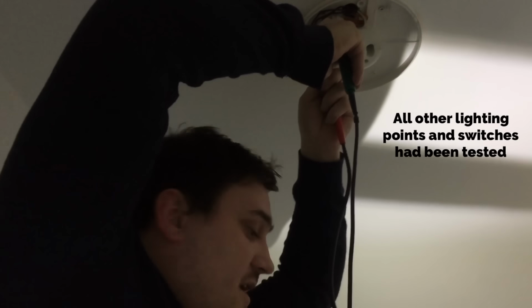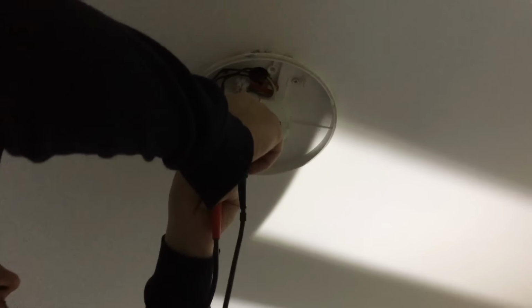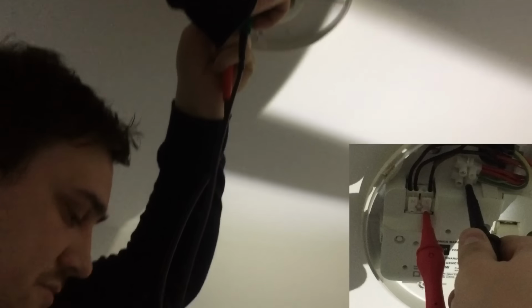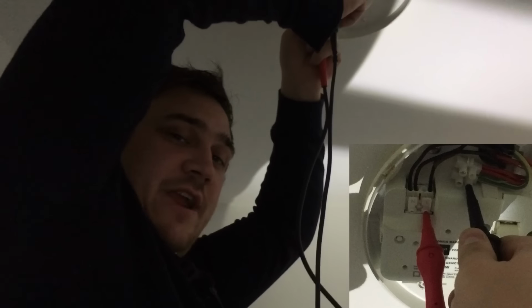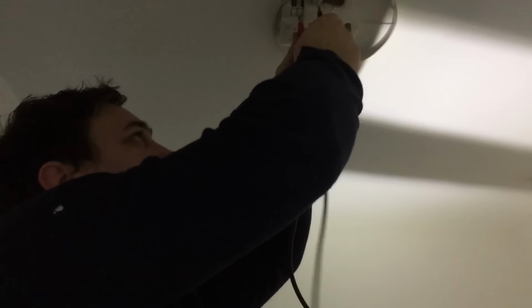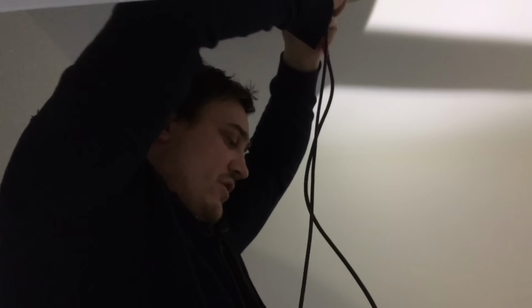Just at the final point of our lighting circuit for the downstairs, doing the continuity of the CPC still. I've probed on, I'll get a reading of 0.73 ohms. Now I'm going to prove polarity, pull in the switch. Now I have an infinite reading, and if I pull it again, I have my resistance reading back.